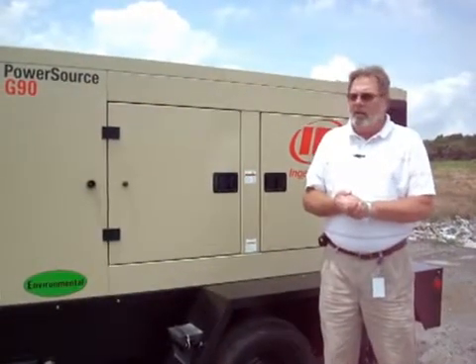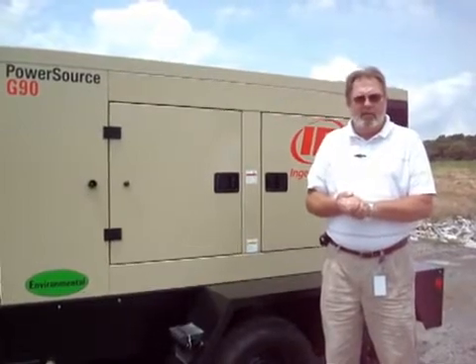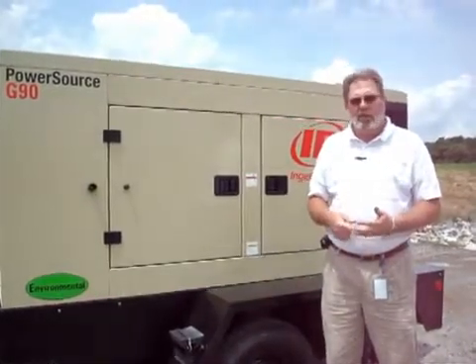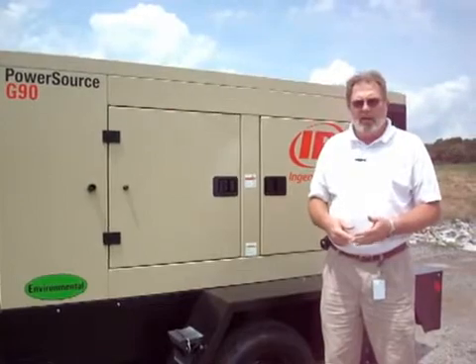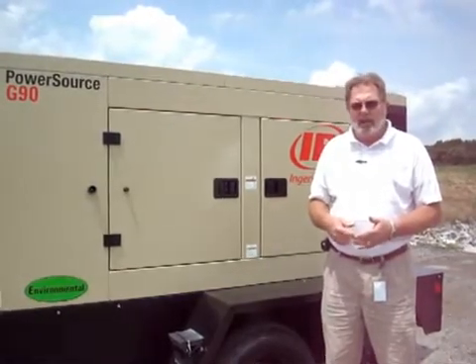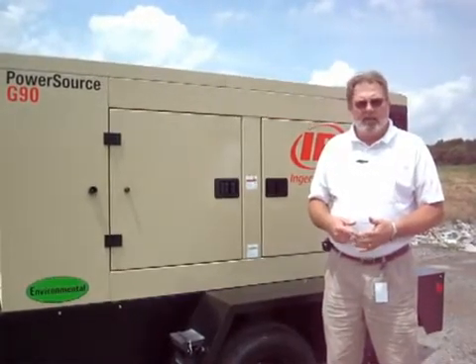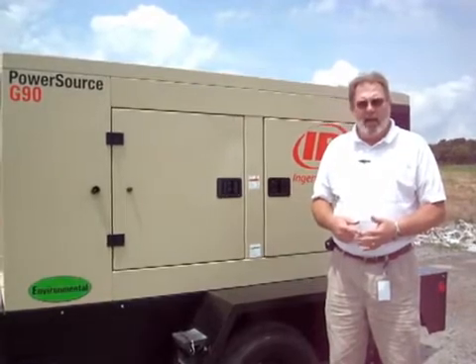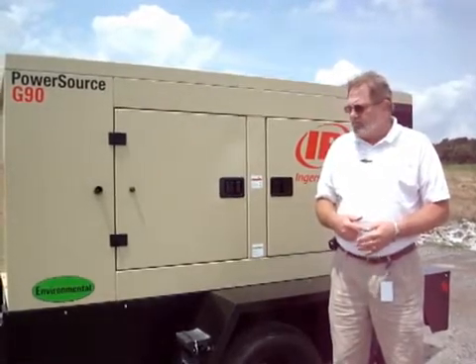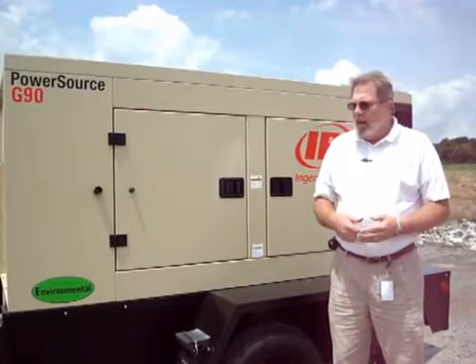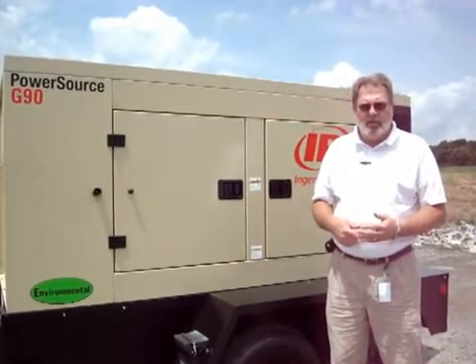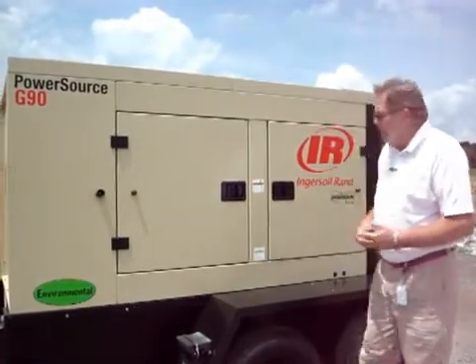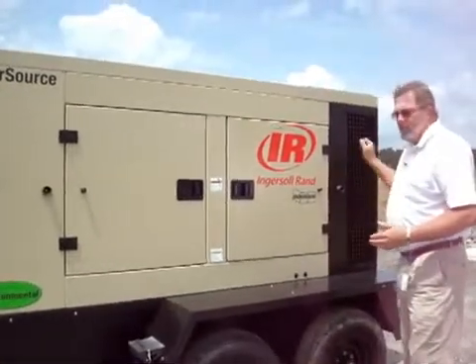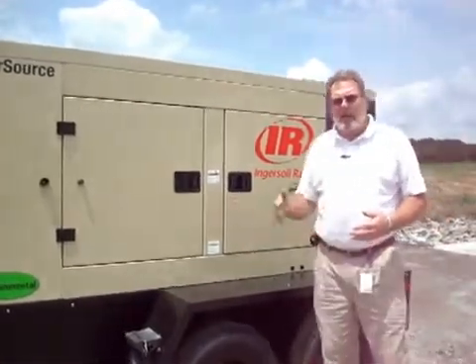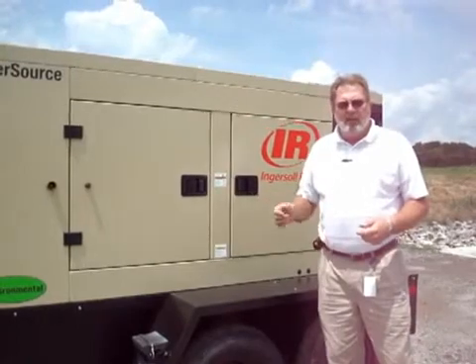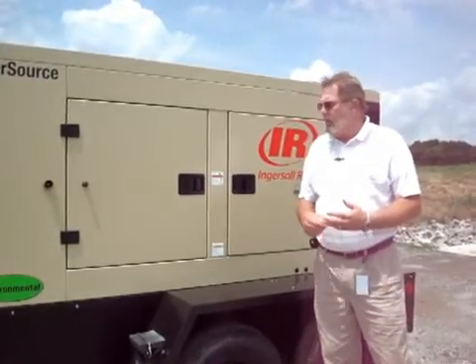Prior to starting the generator set, we have several things we need to check. We need to check our oil level, our water level, make sure our containment area is dry, make sure our connections are hooked up solidly, and verify our ground. And after we do that, we'll look at the outside and inspect our vents to make sure they're clear of any garbage or trash that might inhibit any airflow through the unit for the cooling aspects of that.